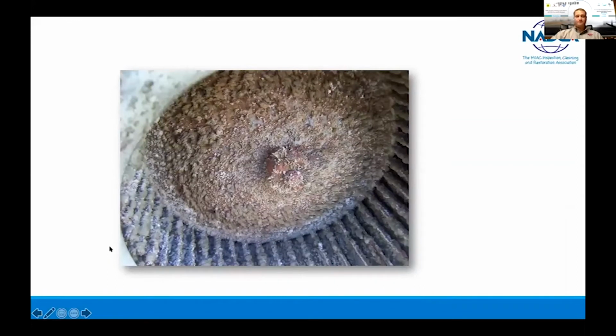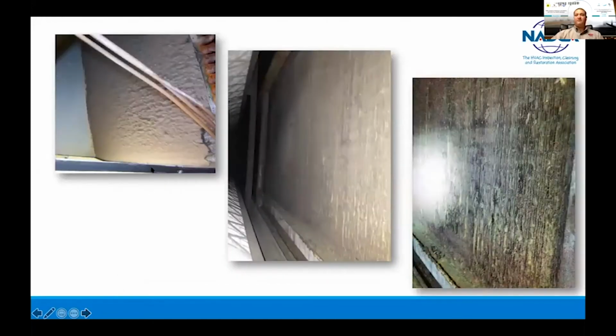Here's a photo of that blower wheel again, just to show the efficiency loss that you would see if it was obviously dirty, not clean. Here are some photos of some coils to give you an idea of some of the soiledness that goes on with these coils. Here on this right side of the screen, you'll see this is more microbial growth based. This here may be more construction based. And if you look up in this upper corner, this is a filter bank. This coil is obviously attracting all kinds of dirt and sediment within the system that is bypassing these filters.